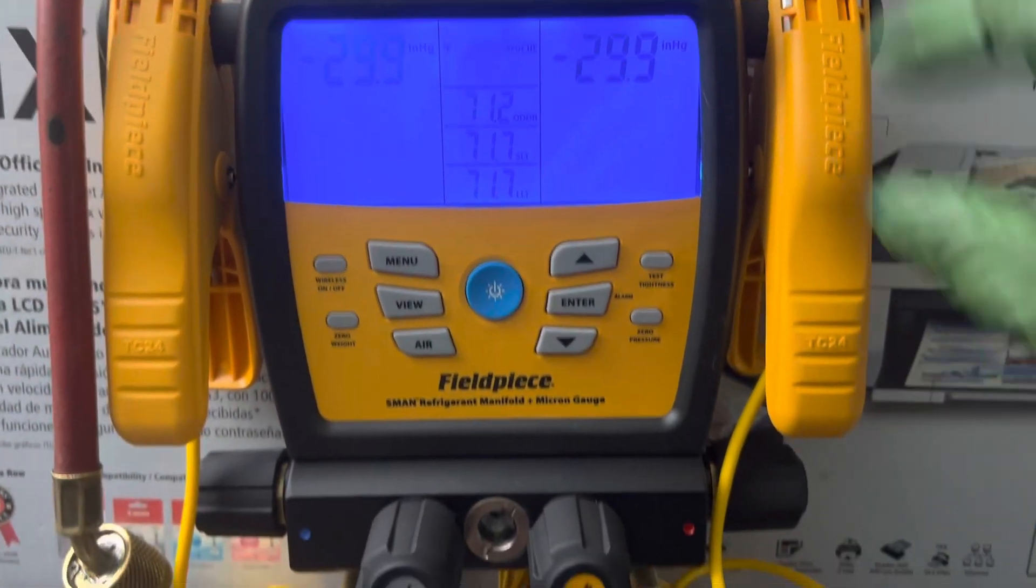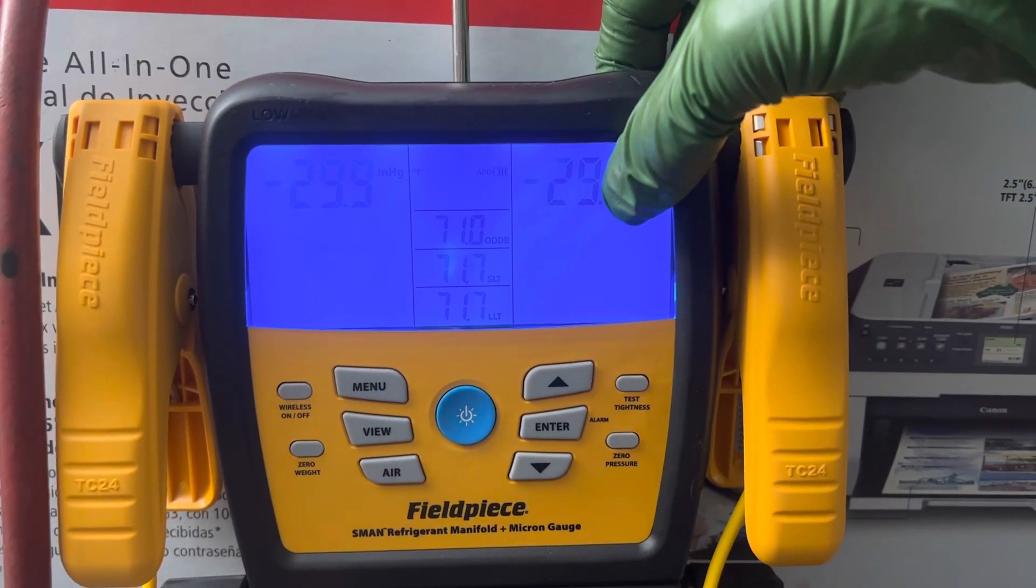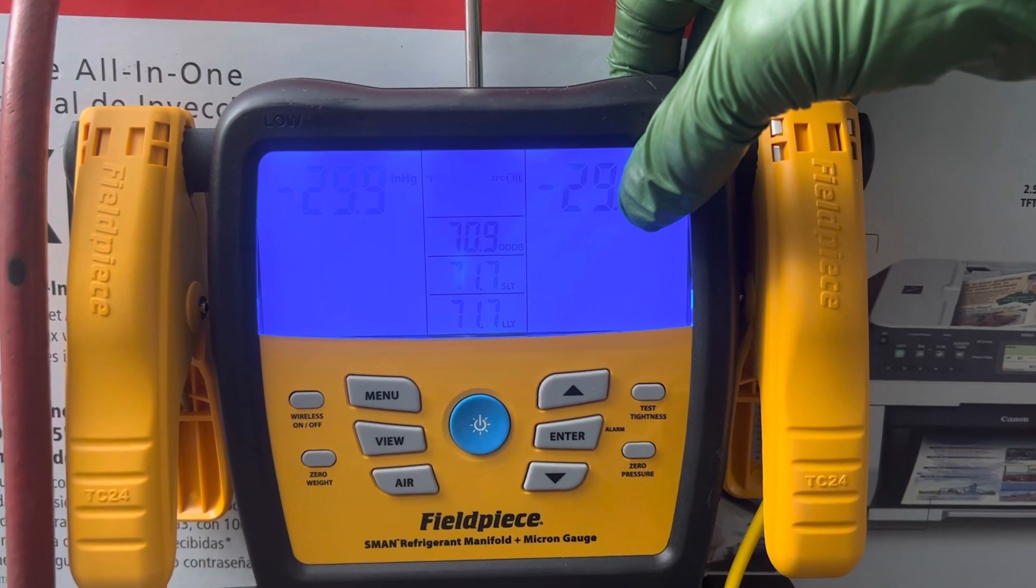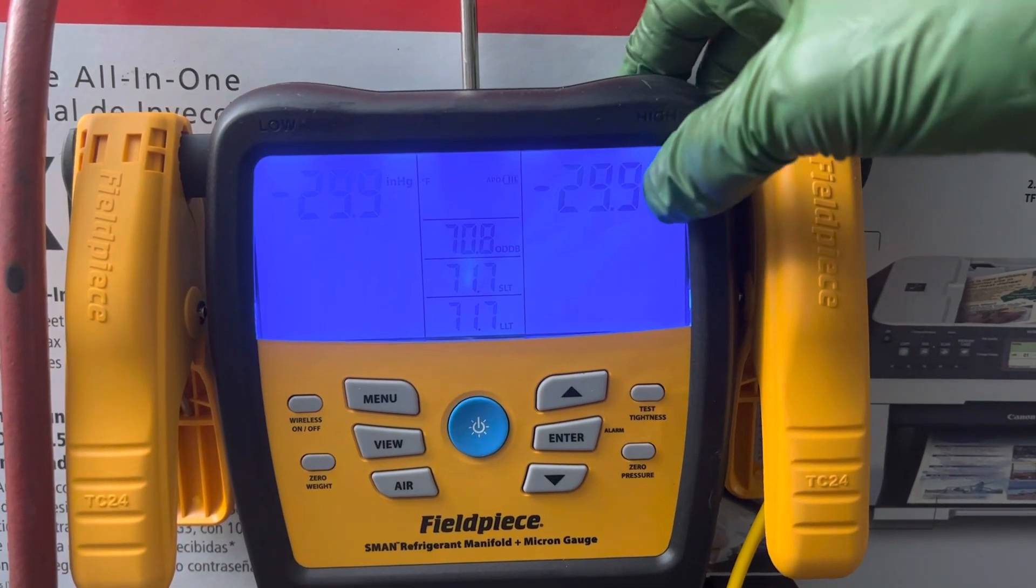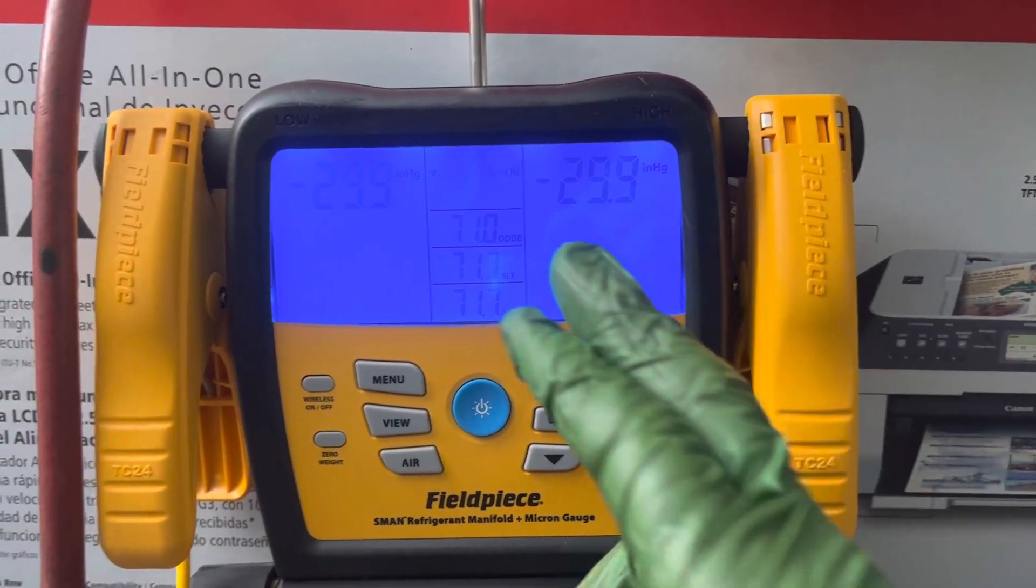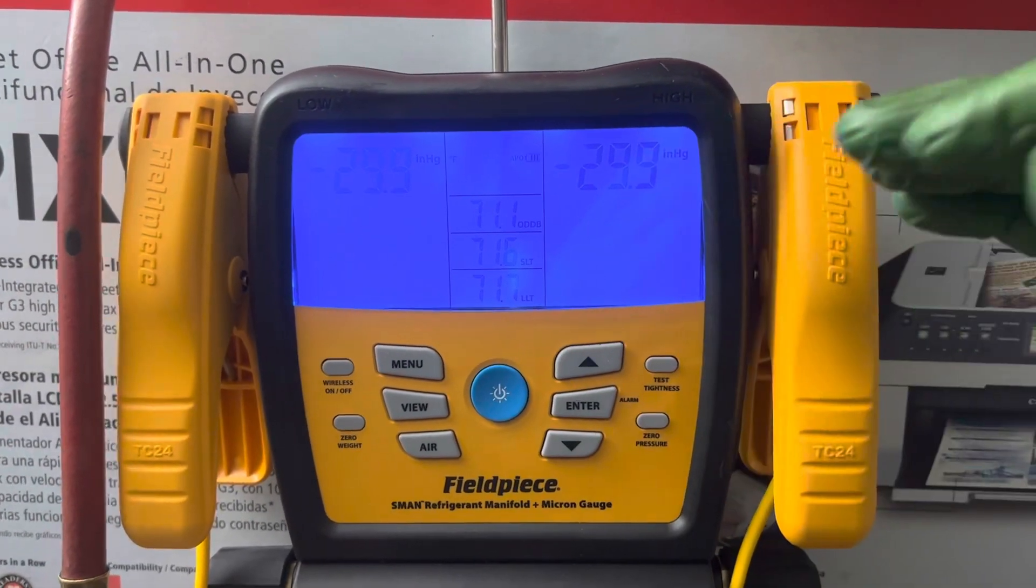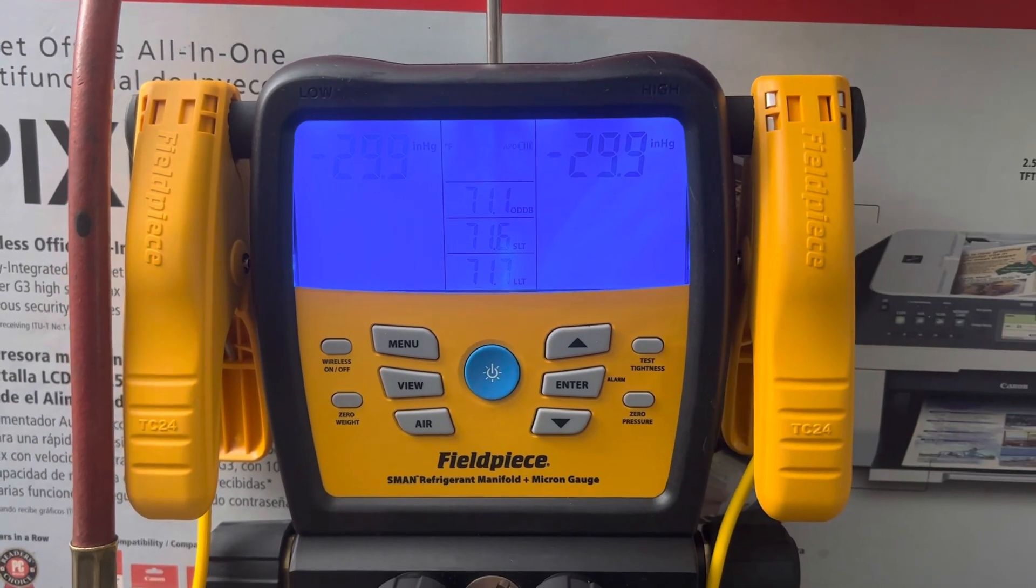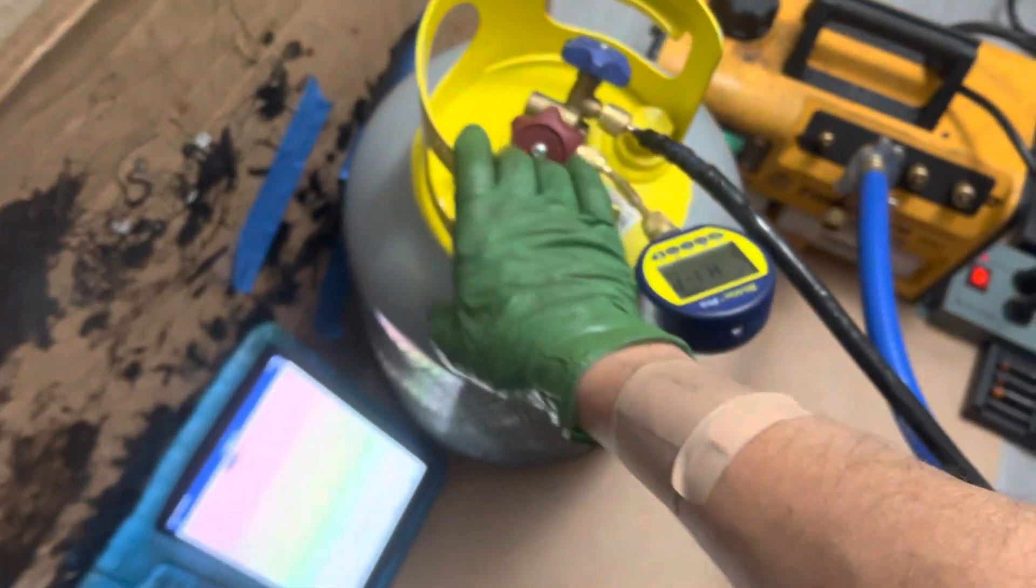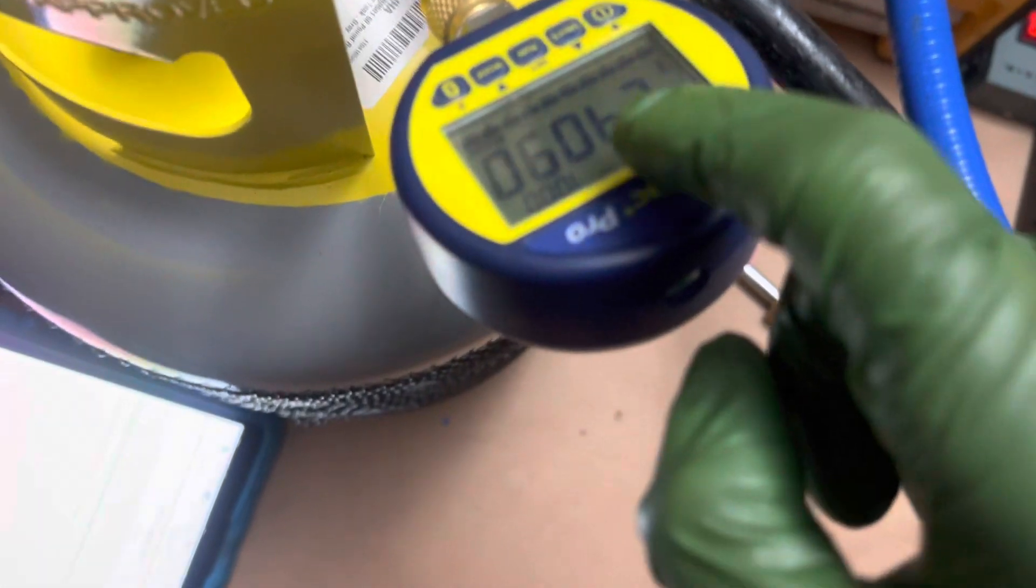Now, this is the limitation of analog gauges: 29 inches of mercury. But with the digital gauges you could go down to 29.9, but then after you get past 29.9, you start getting into microns. We'll be able to read microns pretty soon. Since this is a 50-pound container, this will take a little while. You can see there it goes, it's just starting to read something right now.